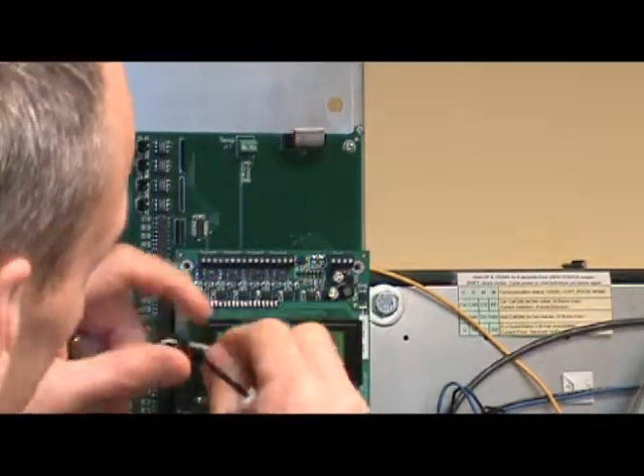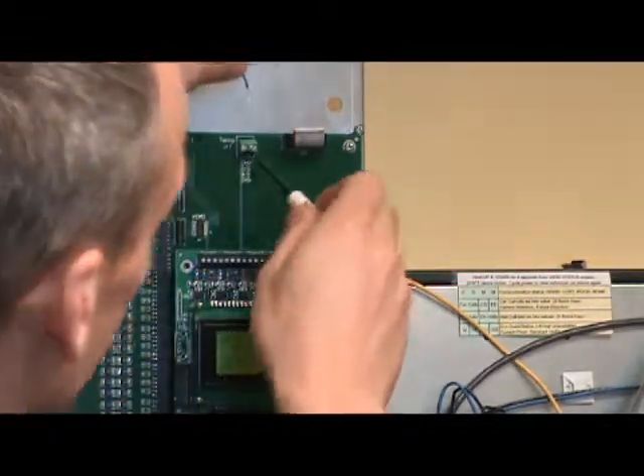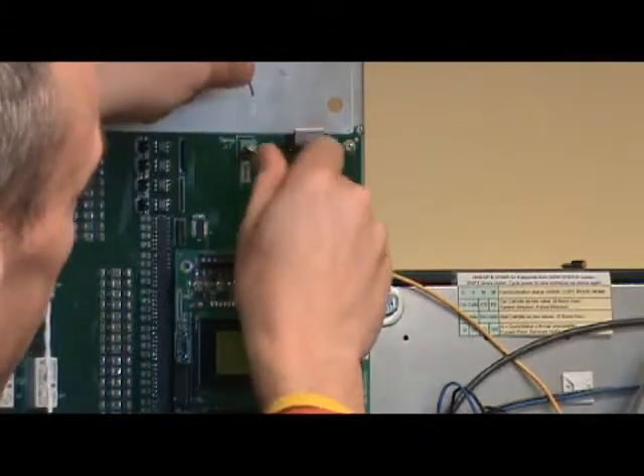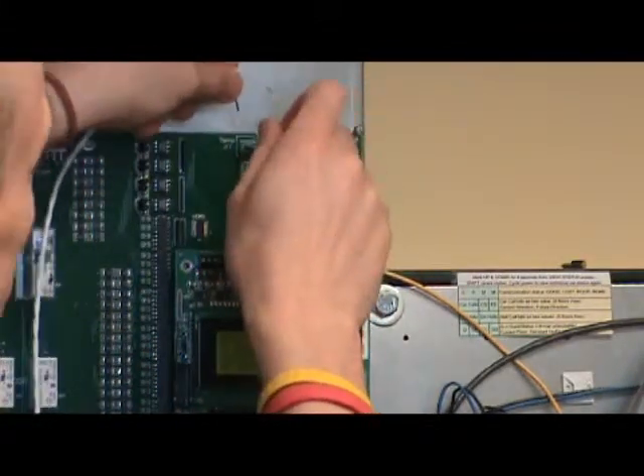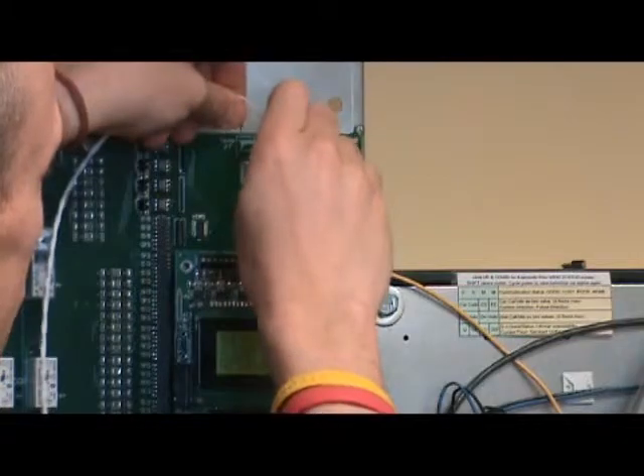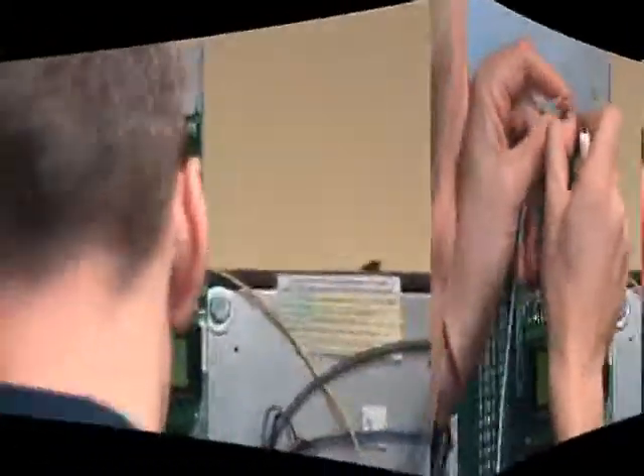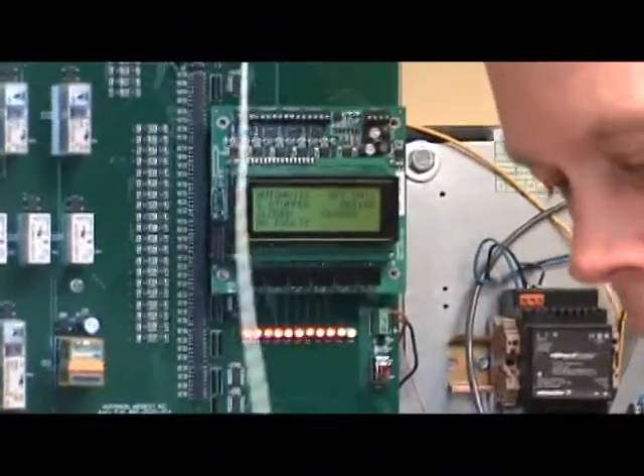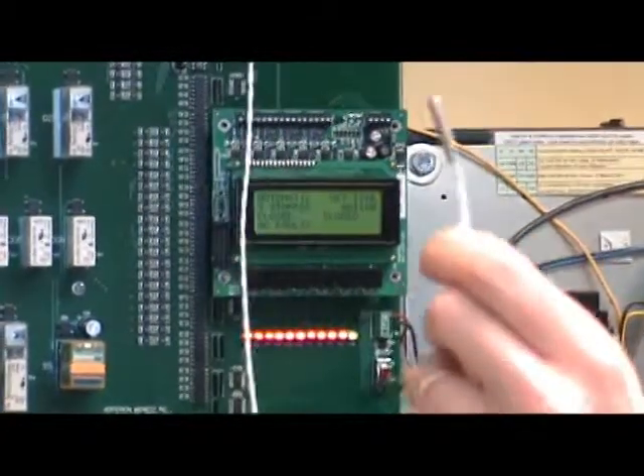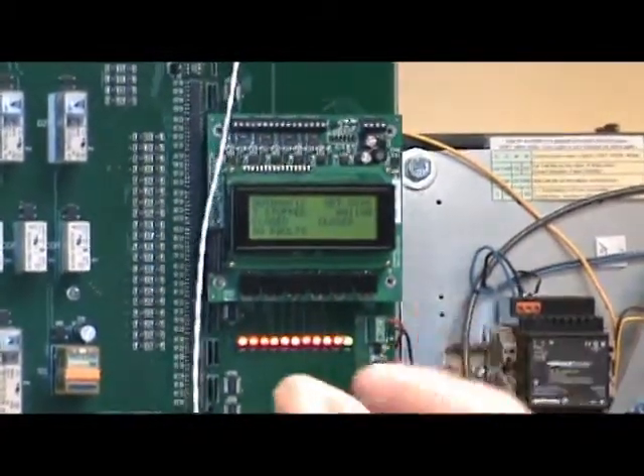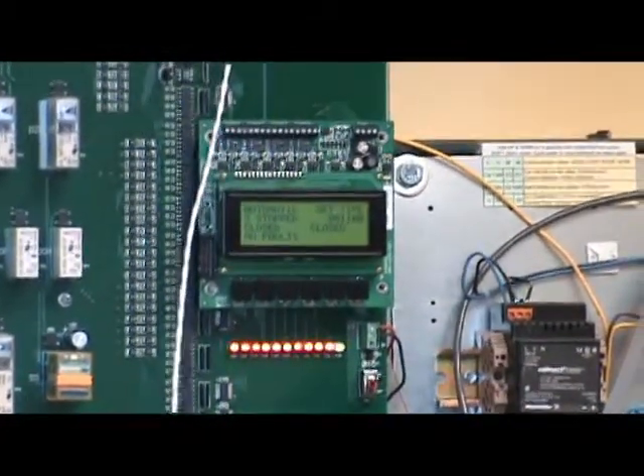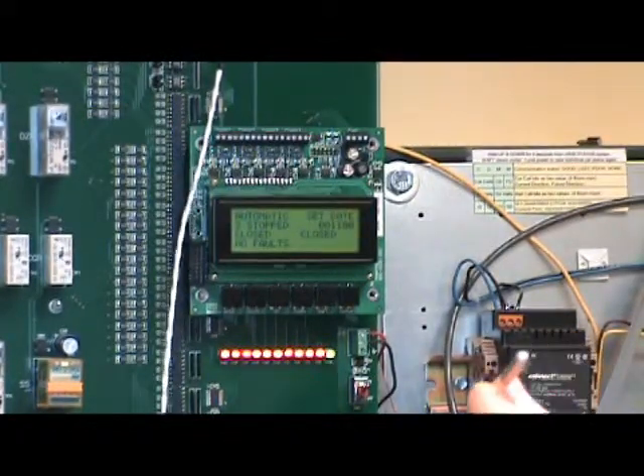Okay, here we go. We're going to wire one lead into each of the terminals. It is not polarity sensitive, so it doesn't matter which lead you put into which terminal. The other end is going to go into the oil reservoir. We suggest just putting it in and zip tying it right to the motor leads so that it's sitting in the oil at all times.